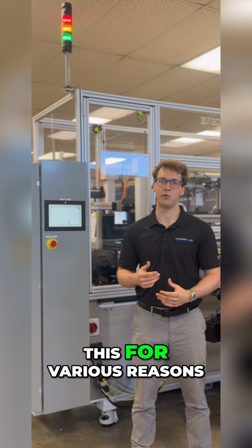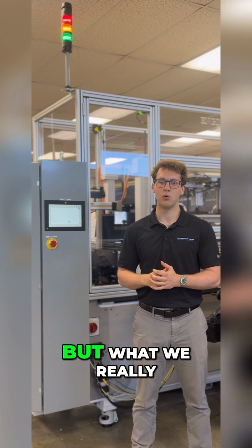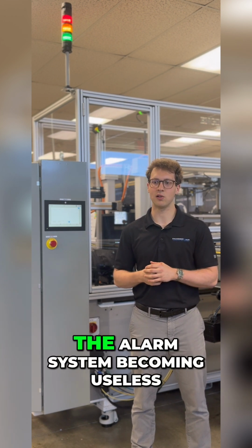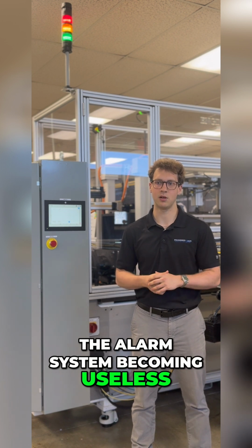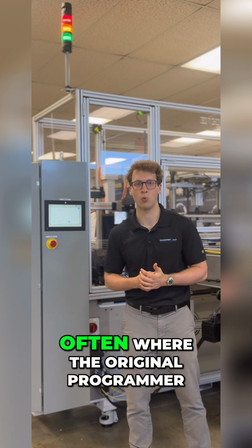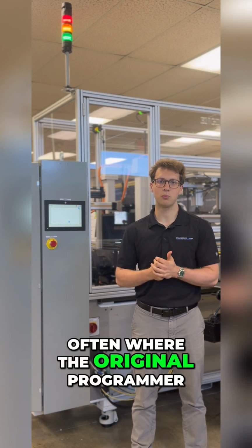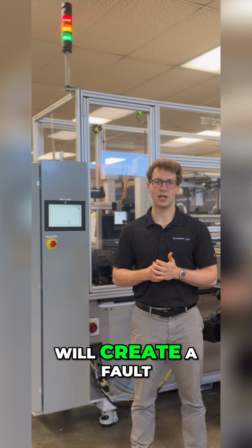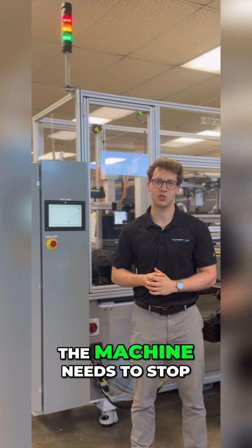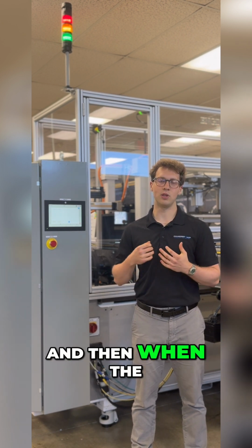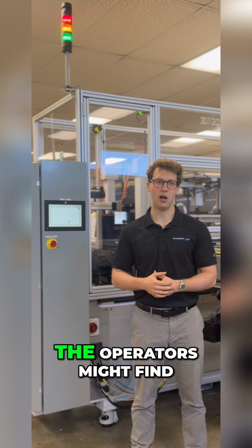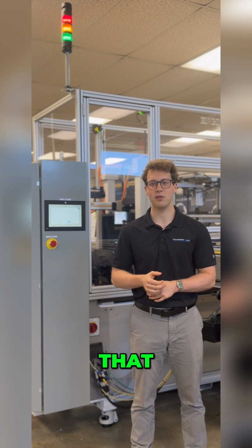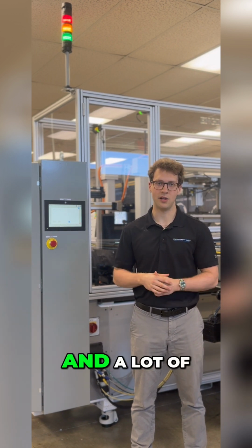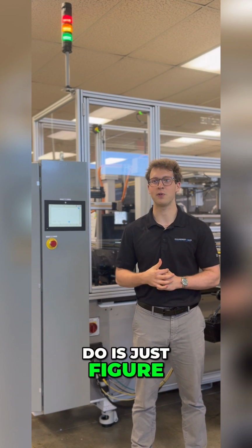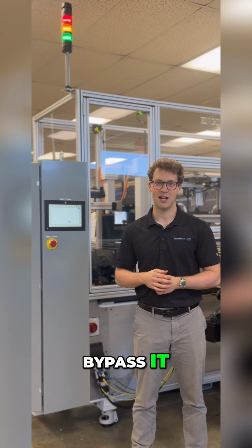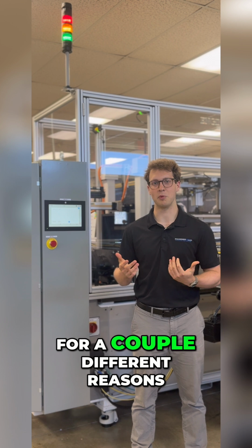And we will do this for various reasons, but what we really try and avoid is the alarm system becoming useless. This can happen pretty often, where the original programmer will create a fault or a reason why the machine needs to stop. And then when the machine's actually in production, the operators might find that fault can be useless. And a lot of the times what they'll do is just figure out some way to bypass it. And that's not good for a couple different reasons.